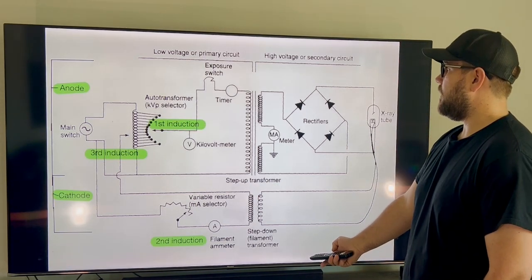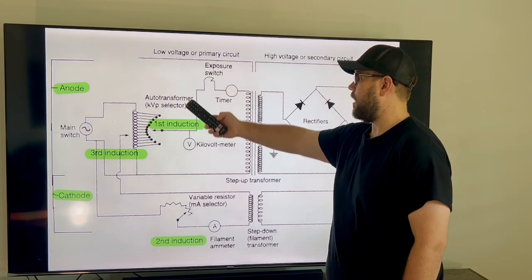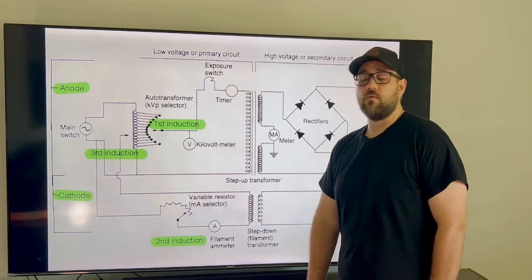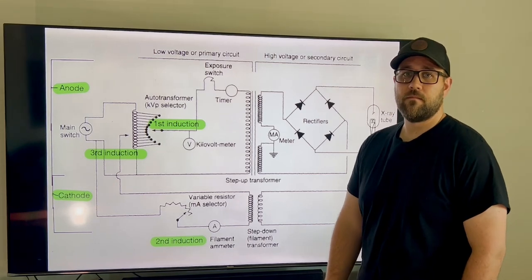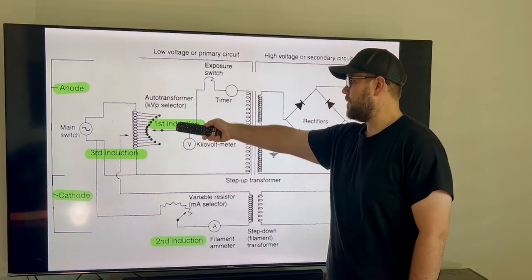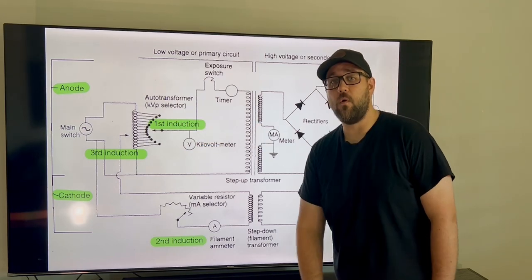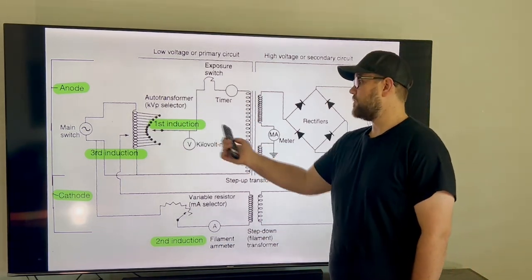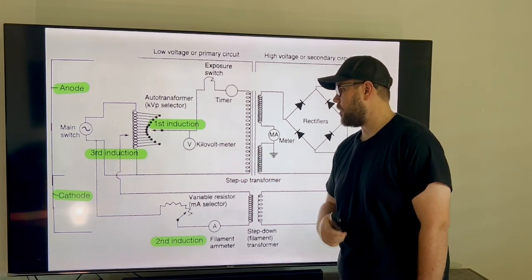So we're going to start off talking about our auto transformer, or where our first induction will be. So we input the 70 kVp, our machine reads that, and it'll actually allow the auto transformer to set itself to the appropriate coil that represents 70 kVp. And it'll be induced from there and read by our kilovolt meter.